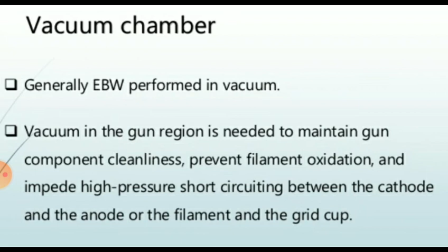Then vacuum chamber, it is required. So vacuum in the gun region is needed to maintain the gun component cleanliness, prevent filament oxidation, and impede high pressure short circuiting between the cathode and the anode, or the filament and the grid cup.